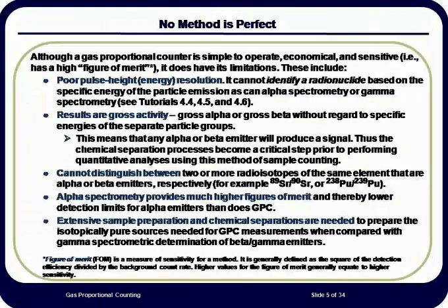Some instruments have the capability to provide the user with spectral output of accumulated counts versus energy. However, due to sample self-attenuation for alpha emitters and the broad energy spectrum of beta particles, these spectral outputs can only provide very general information regarding the potential of radionuclide cross-contamination of the final sample test source that is counted.